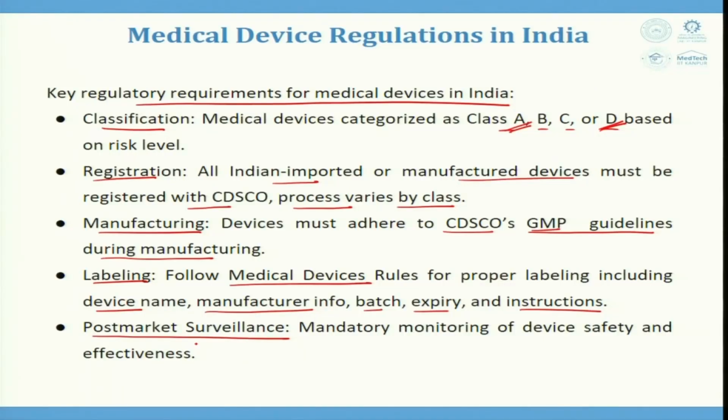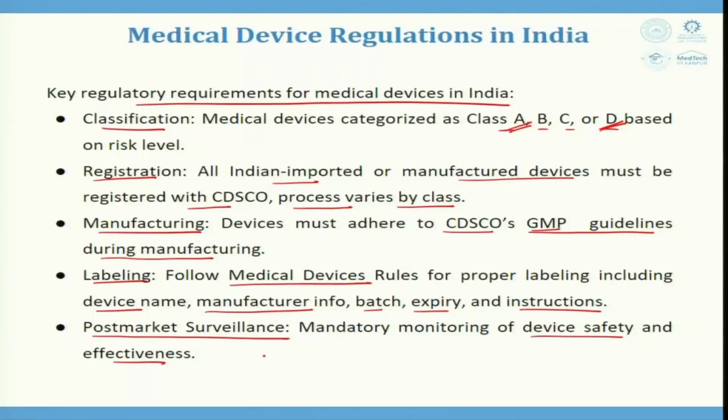Then post market surveillance. Post market surveillance means mandatory monitoring of device safety and effectiveness, which includes data analysis on adverse events, recalls or complaints. Post market surveillance is always there. The medical devices which are replaced, or medical devices for which complaints have come, and how quickly you have addressed the complaints, all these data points are to be kept in the register.